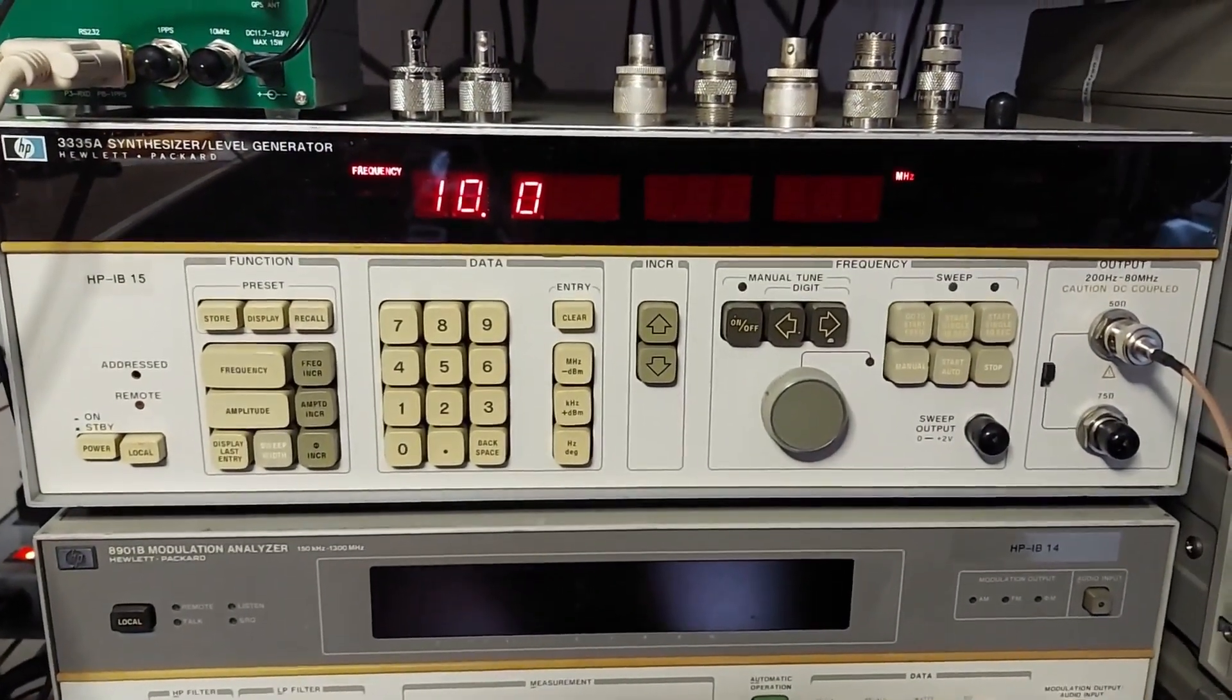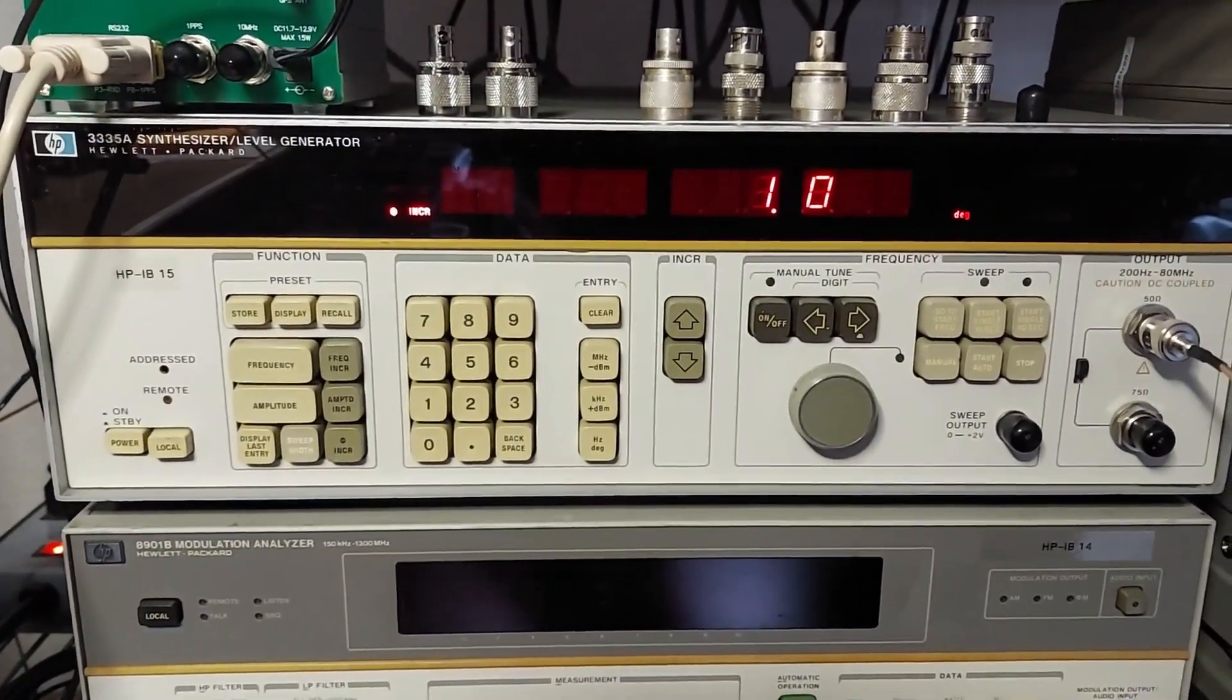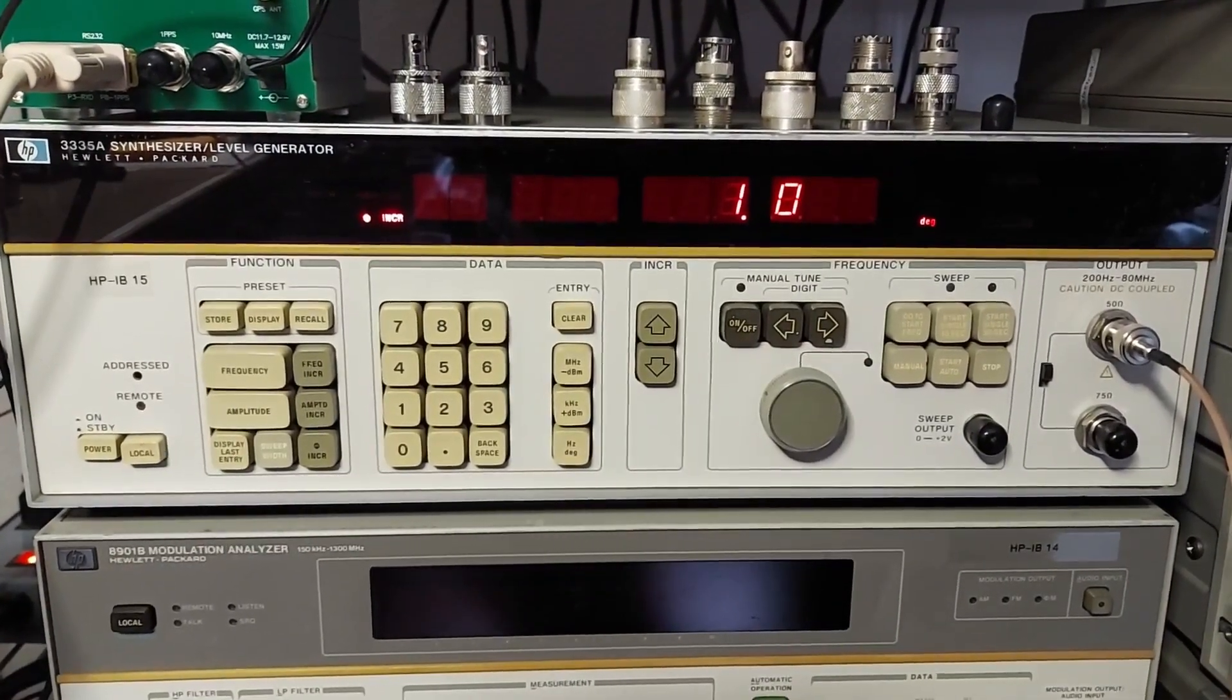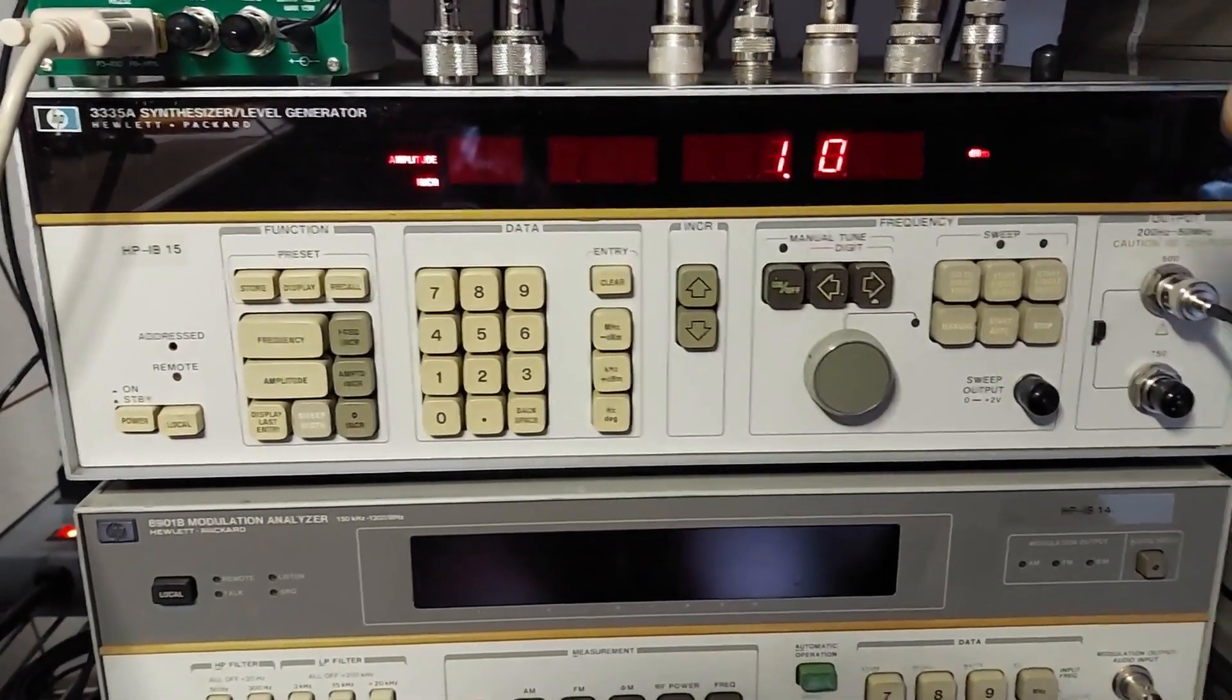Now there's some other functions here best used in conjunction with the increment buttons here. This will allow you to set the phase. This button here, it's the phase increment button. This allows you to set the phase relationship between the 10 megahertz output on the back of the instrument and the frequency output jack on the front, and I'll show that here in a few minutes.